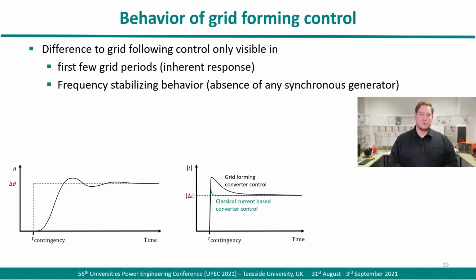Regarding the current, we can see the difference between the grid following converter and a grid forming controller. At the moment the contingency happens, there is an angular mismatch at both controller types. Grid following control will find the angle very fast and adjust its output voltage.